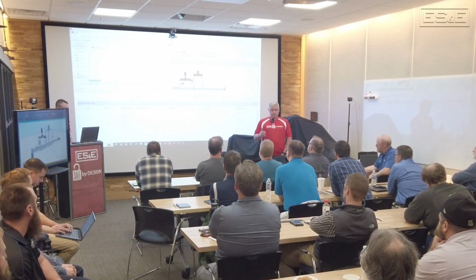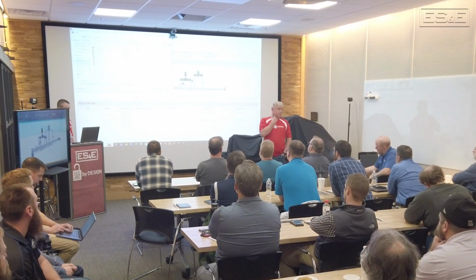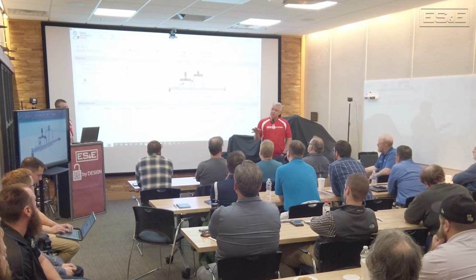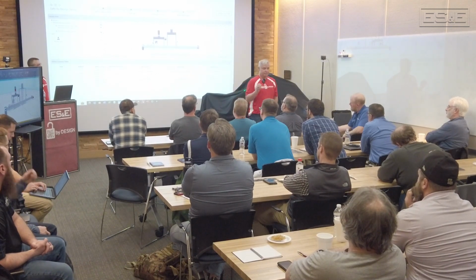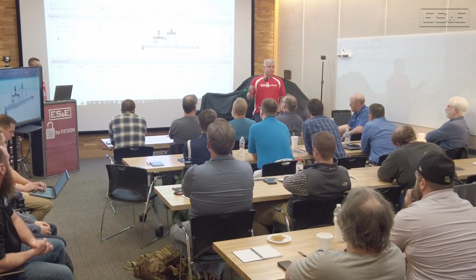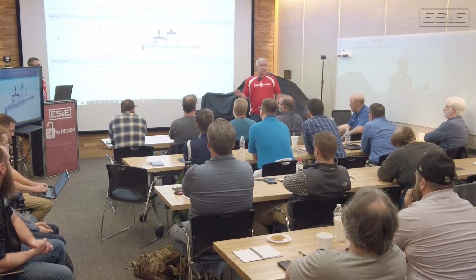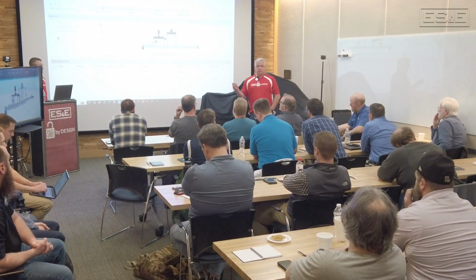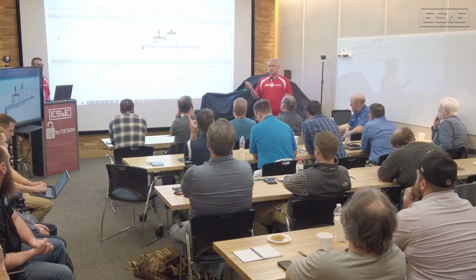The other reason that we're using the 527 is because I can do safety over Ethernet, CIP safety. Once again, I don't get to sell any I/O modules, but that's cool because I don't have to do any safety wiring. So that is why we use the 527. No hard wiring for safety. The control is done via the Ethernet cable to actually control the drive, but it also makes it safe, using CIP safety.